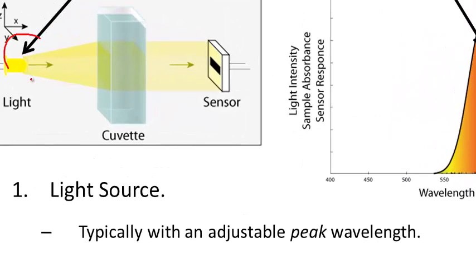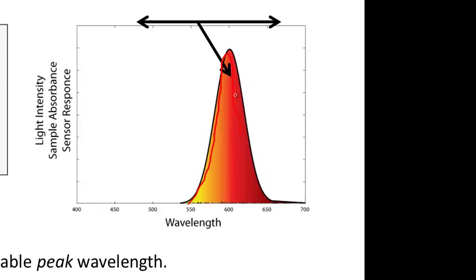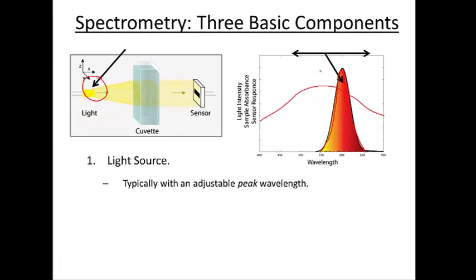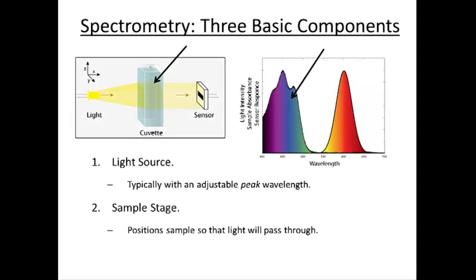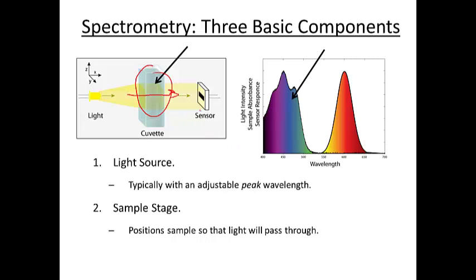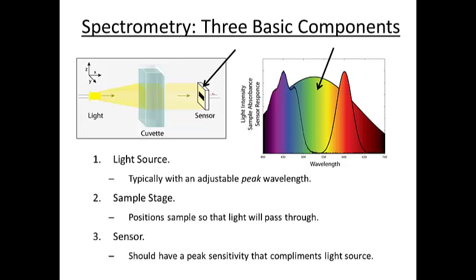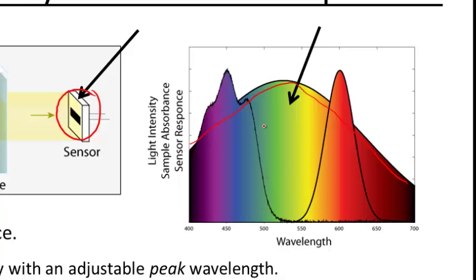Just a basic spectrophotometer, how it works. We've got a light source. That light source puts off certain intensities of light at different wavelengths. We might have a red light source, blue, green. We might have white, so it's a broad spectrum. But, it's typically adjustable. We can move that light source one way or the other. Look at different wavelengths. We also have some sort of sample stage through which light may travel. In that sample stage, in this case we have a little cuvette, which has our liquid sample in it. This case is beta carotene. It has some spectrum, and that's where that sample would absorb light. Then, we also have our sensor that detects light. This could be very broad or it could be very narrow. Maybe it's adjustable. We can use two different sensors for different wavelengths. But, it does have some preference for absorbing certain wavelengths of light.